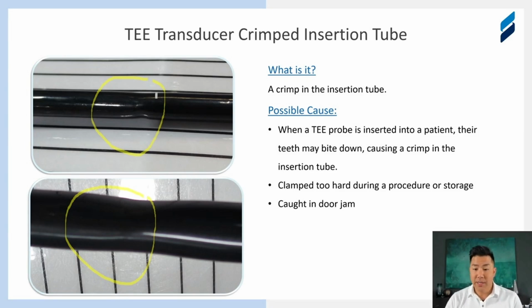Another way it's caused is, sometimes there's clamps used with these transducers, and they just clamp it too hard around the insertion tube, so it squeezes and it crushes it down. And another one that we see surprisingly more often than we'd like, it gets caught in a door jam. So, the TEE probe's being carried around a hospital or a healthcare facility, and you're going through a door and the door closes faster than you think, and boom, it catches the TEE probe in a door jam. Again, it happens way more often than we ever thought it would, but hey, it does happen.